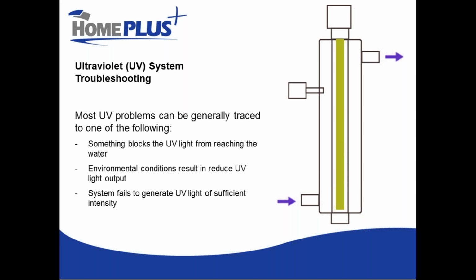The lamp becomes less effective. And conversely, if something's interfering with that cooling process, or we're drawing really hot air into the system, as the lamp gets too hot, we can also have problems with output as well. So environmental conditions can certainly play a role. And then, of course, we can have a problem where the system itself is just not generating UV light of sufficient intensity. So those are really the root of the problems.